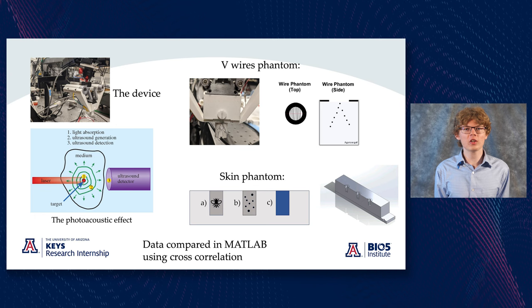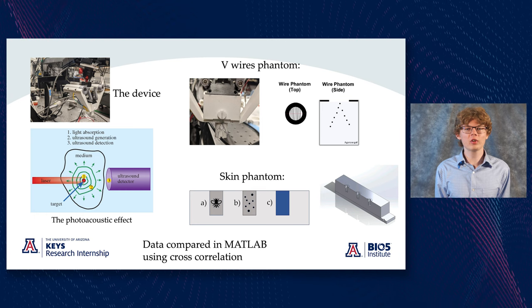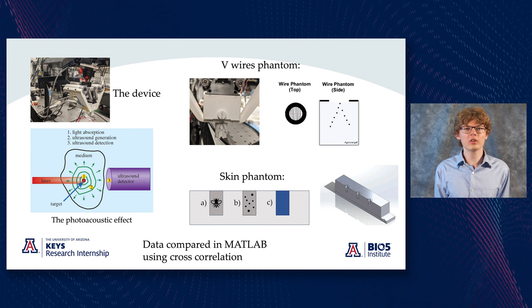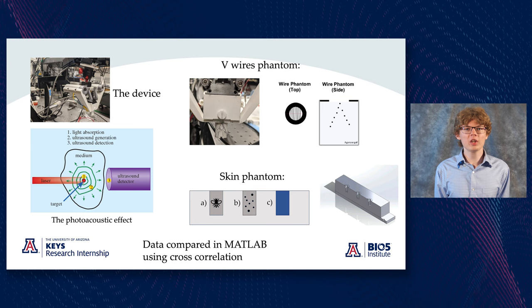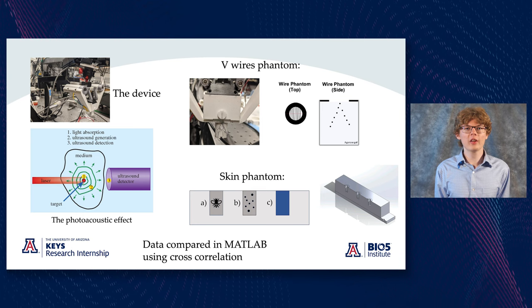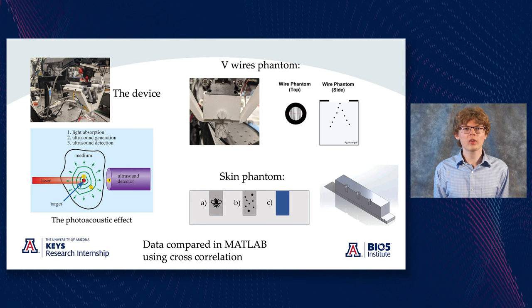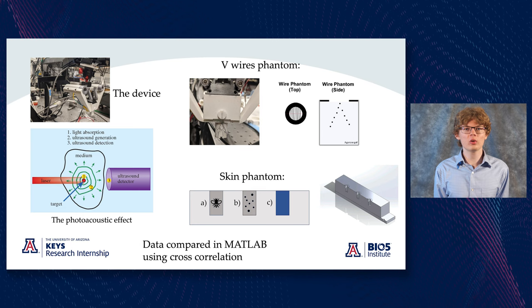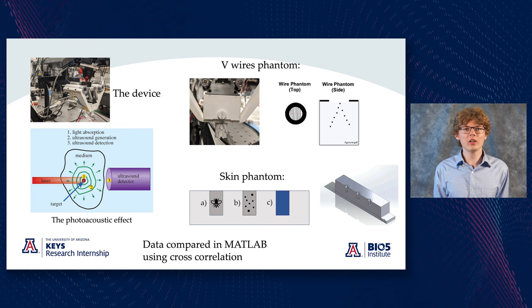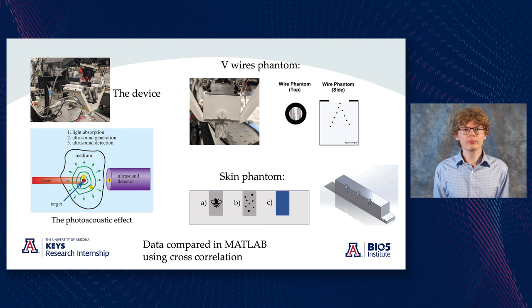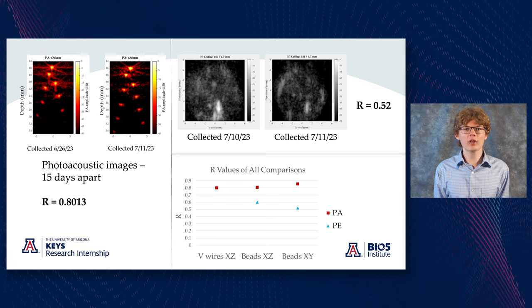To show its abilities, I used two skin phantoms, one of which I designed in SolidWorks and 3D printed. It included three different tubes with three different types of materials: a dead bee as an example of a complex biological structure, small beads to show resolution, and methylene blue gel to show multi-spectrum imaging capability. The other phantom had wires arranged in a V-shape to show 3D imaging capability. We took images over multiple days and compared data in MATLAB using a cross-correlation algorithm. We found that while the device cannot produce reliable ultrasound data over time, it can produce reliable photoacoustic data over time.